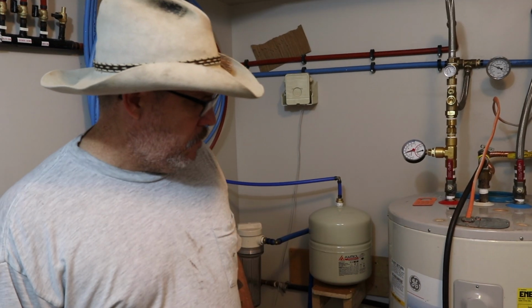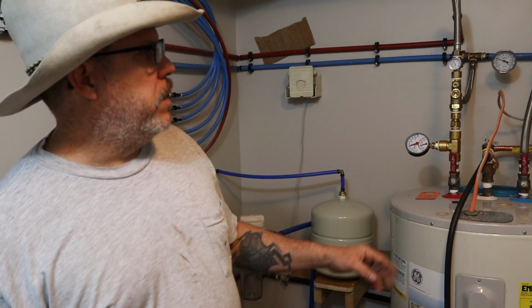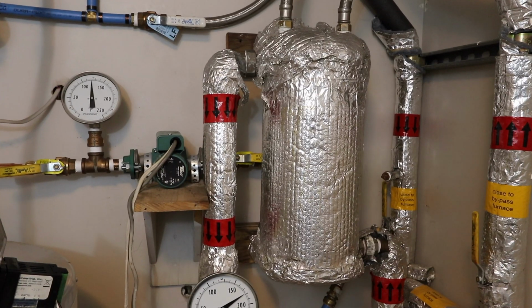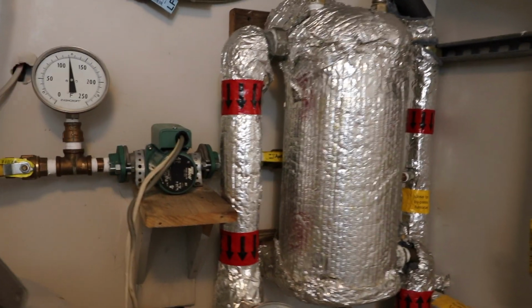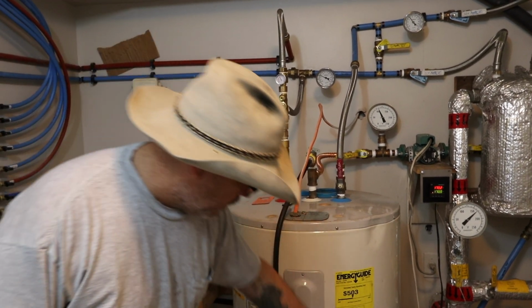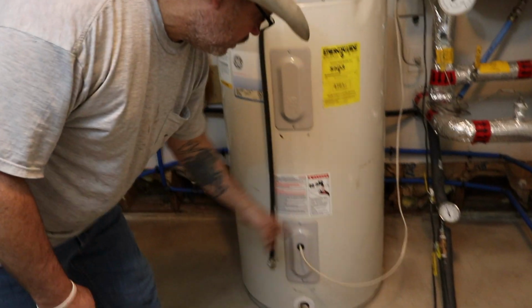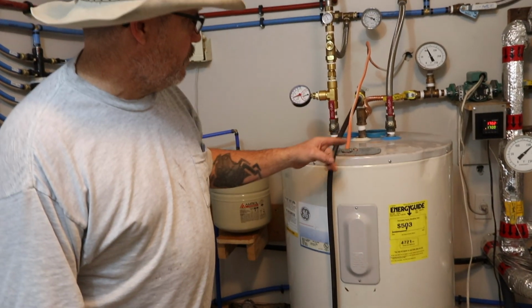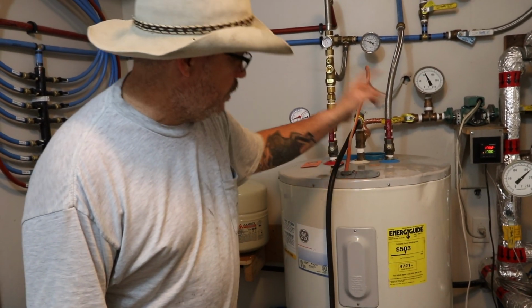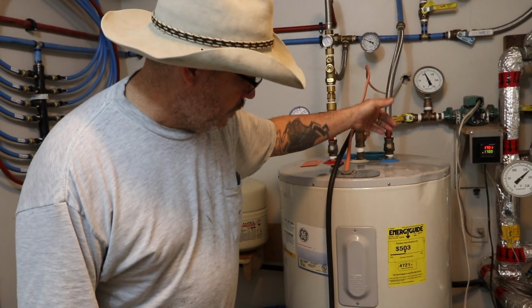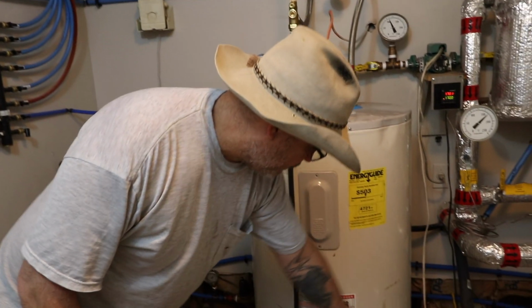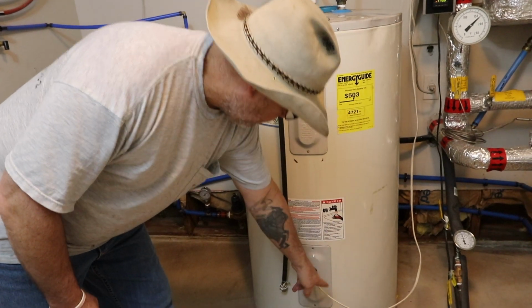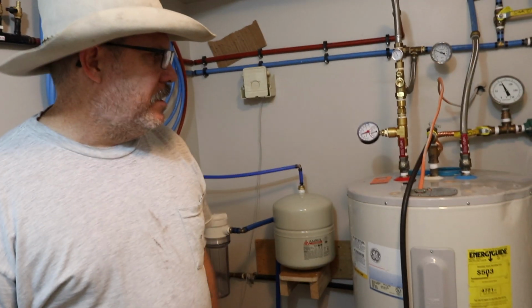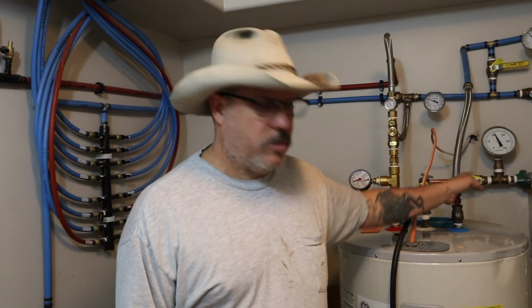That's my main way of heating my water, but I do have another heat exchanger I put in as an afterthought, simply because I've got cold water coming in and the dip tube is down low. Once this circ pump kicks on, it's pumping water out of the water heater to the boiler and back through a heat exchanger in the boiler, and it comes back fairly hot, but I was clashing my temperatures in my water. So I said, well, why don't I just preheat all of my cold water so I won't have such a big delta T down here at the bottom of the water heater.